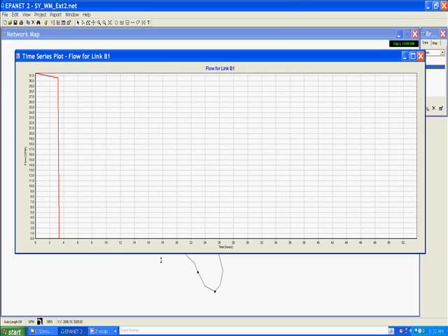Because the demand was so low at 0.35 gallons per minute for just the 4 homes, the pump did not have to come on again because the tank did not go below the 6 foot level again.